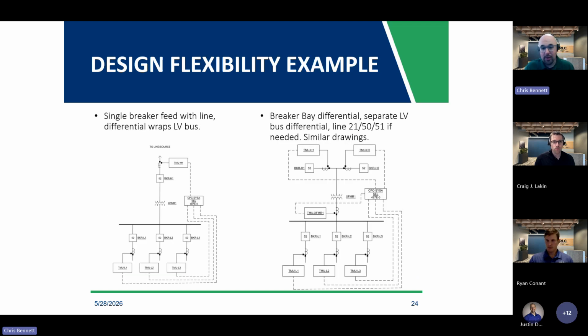As a little bit of an example here, as a mock-up, we have the typical design example that we've been seeing through this presentation on the left. Single line in to a transformer, feeds a low voltage bus out to 3 feeders. What we would see in this design, even with CPC, is you would still have the breaker diagrams for trip coils, close coils, but because they will have the relay or the merging unit inside of them, a lot of them should be repeat values and repeat sheets, reducing the amount of time and customization for each individual breaker. The tripping and the statuses are all brought back into the centralized protection area to be used as the engineer sees fit.